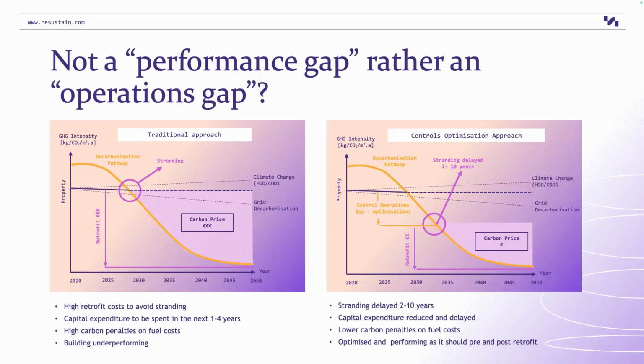But what people tend not to do is ask, is this building performing as it was designed? What's wrong with it in order to fix it? So the first thing to do is look at the control inefficiencies, and this is what I call the operations gap. This is where we're finding about 30% savings in energy, a significant amount that can delay the asset stranding by quite a few years just by reducing that energy usage. Not only have you reduced the energy usage, you've found where the issues are with the building. So what you might have thought was a facade issue actually isn't, it might be a lighting issue, or a cooling issue.